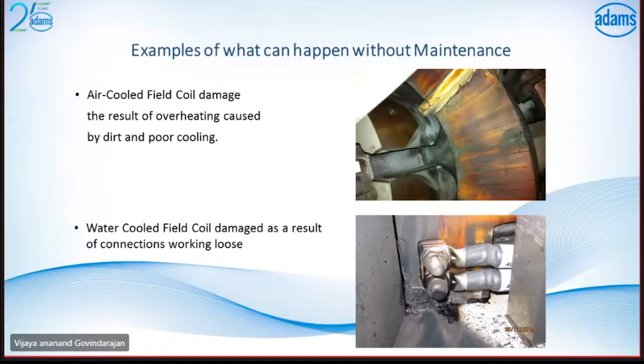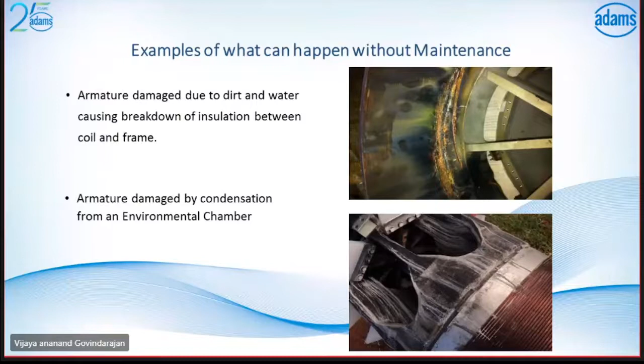We use chambers in combination with vibration testing. When we are using a chamber, we need to properly maintain the dust seal of the chamber as well as the seal of the shaker. If by mistake any condensation happens and water goes inside, it will condense inside the armature and that may cause a short circuit, thereby resulting in the failure of the armature. That is what is seen in these two images.